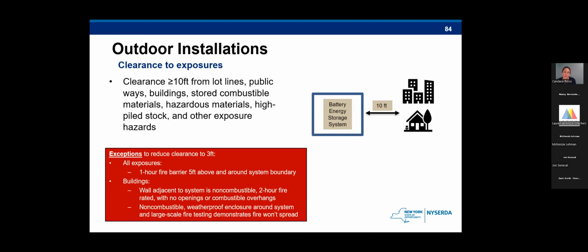So basically they have a specific clearance to exposure requirement. For all projects, they need to be at least 10 feet from lot lines, public ways, buildings, and really anything. And that's used as a fire barrier. This distance can be reduced by either large scale fire testing or placing a fire barrier between the storage system and the structure. The fire barrier should be at least 1 hour fire rated. The second option is for the building that is adjacent to energy storage to make sure it's non-combustible and has a 2 hour fire rating with no openings or combustible overhangs.